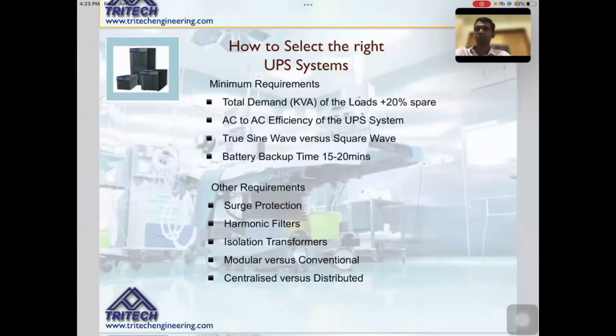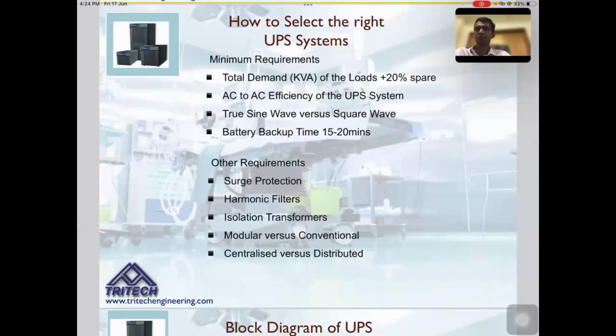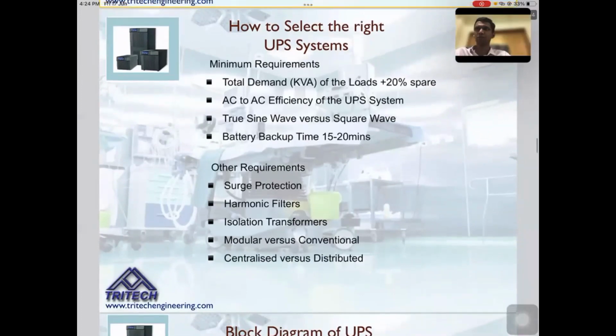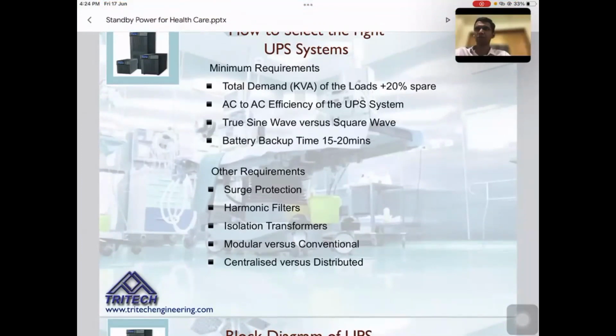Other requirements are surge protection, harmonic filters, and isolation transformers, which provide galvanic isolation. Again, these isolation transformers are required only if it is mandatory, because generally they reduce the efficiency of the overall system. And then there are other parameters like modular UPS versus conventional UPS, and of course, centralized UPS versus distributed. Why I'm saying this is that many medical equipment vendors bring a dedicated UPS system with their equipment. Again, this is one topic which needs to be discussed separately, because it adds cost to the maintenance, since you have several batteries distributed in your building. It is always better to have a centralized one feeding every equipment. This is why this point is discussed.